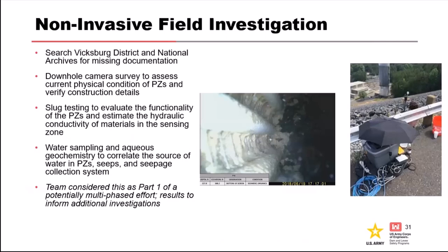So we scoped that. We wanted to verify construction details because we didn't have any information. Where's the screen? What's the condition of the pipes? Do we think that the filter pack is potentially plugged? So we wanted to get an idea of general condition. Do we have broken riser pipes? That was another theory we had about why that instrument is tracking so high but still with the reservoir.